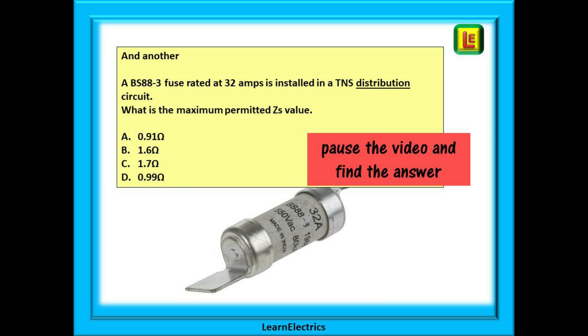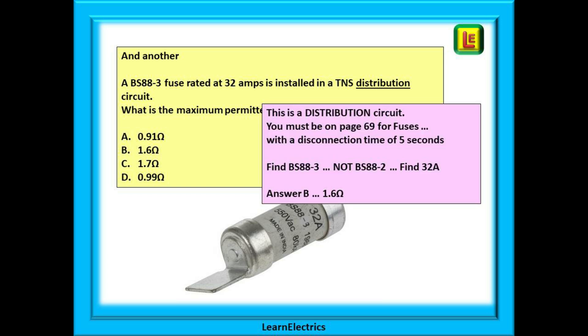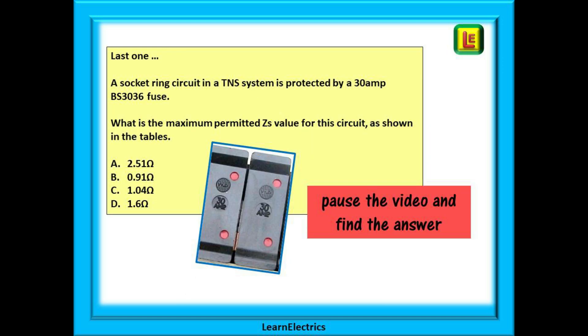Another question now. A BS 88-3 fuse rated at 32 amps is installed in a TNS distribution circuit. What is the maximum permitted ZS value? Again pause the video and attempt the question. This is a distribution circuit and it is a TNS earthing system. You must be on page 69 for fuses table 41.4. Those with a disconnection time of 5 seconds. Find BS 88-3 not BS 88-2. Find 32 amps and there is your answer. Answer B, 1.6 ohms.